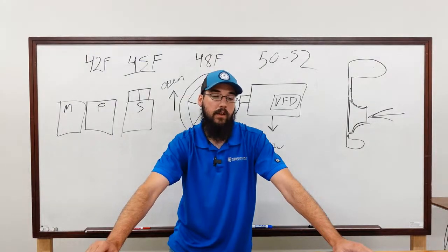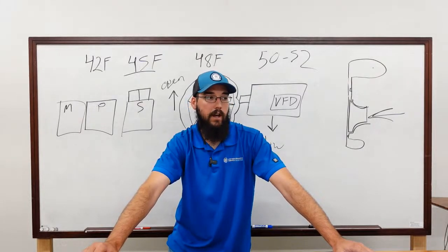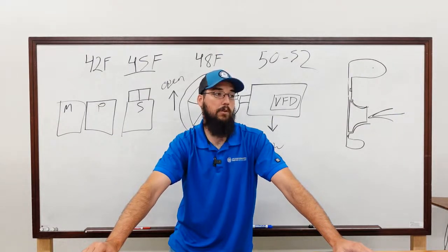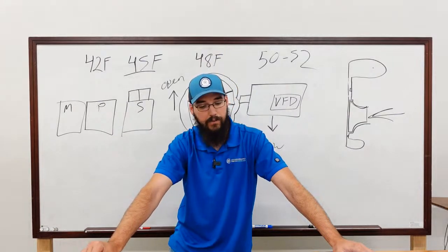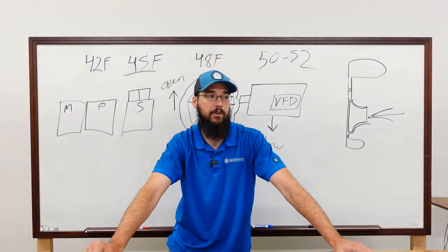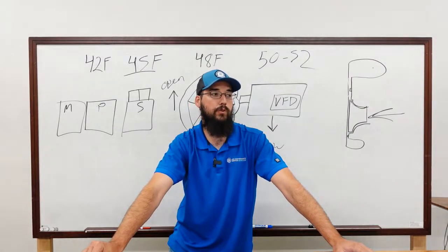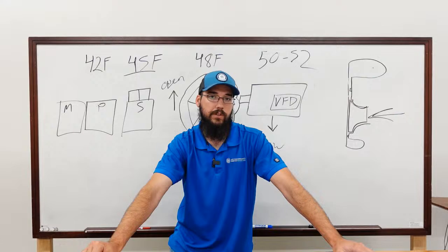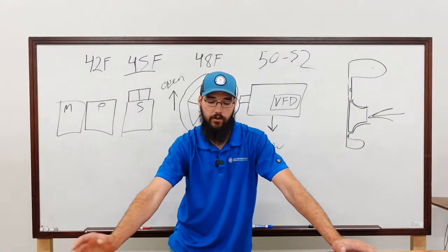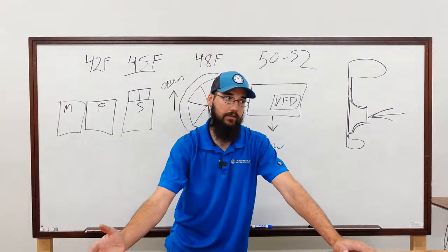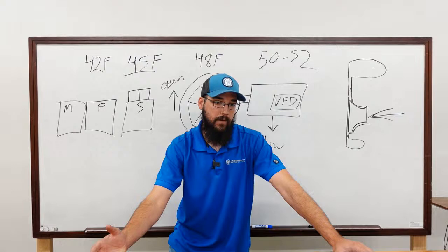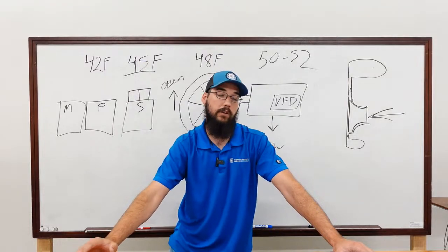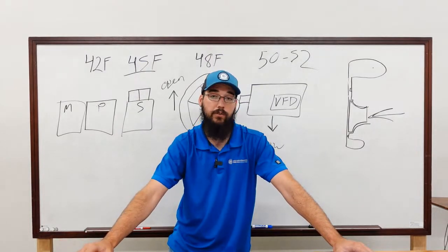while it's spinning. And this is one of the best tools you'll ever have working on specifically centrifugals, is your hearing. Now, they're typically very loud machines, some much less than others, but anytime you're around a centrifugal, you need to start listening. You need to really tune your ears to the noises that it's making. Because as you begin to learn each of those sounds, and it's going to change slightly, a CVH stall doesn't sound exactly like a YK stall, but they're not that far apart either. So anyways, it's something to pay attention to. You can hear the stall condition begin to build, and you can hear it get worse and worse until eventually you cross that threshold and it goes into a surge.